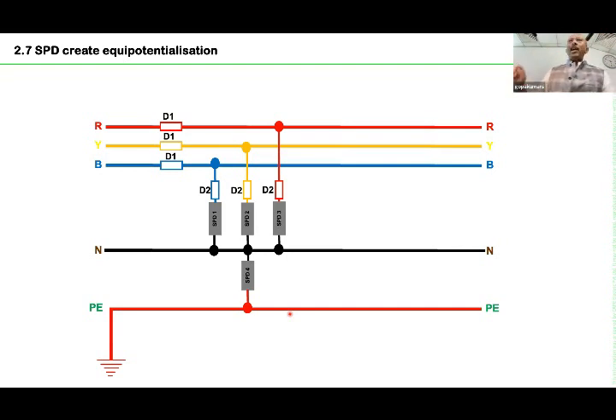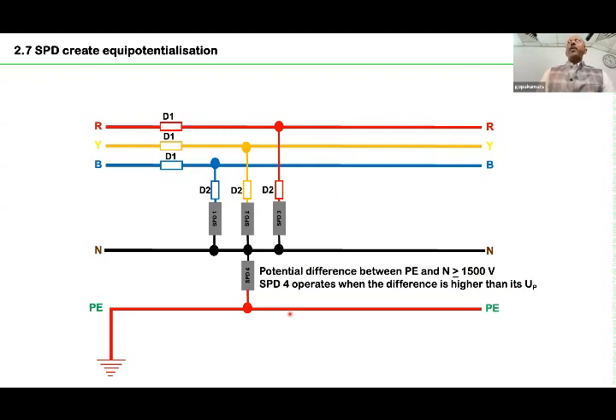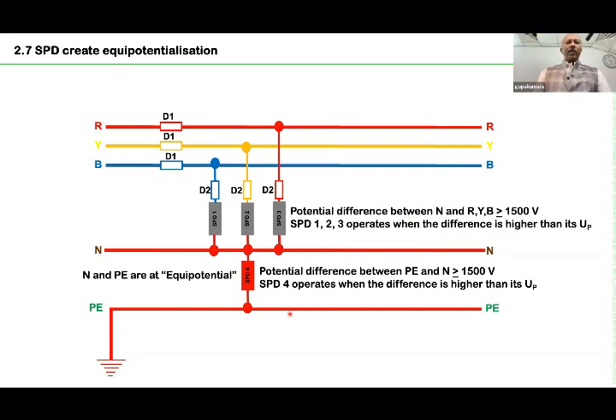Then what happens? Now the potential of the earth wire is very high. SPD number 4 operates and it connects the earth and the neutral. Suddenly your neutral and earth are connected together very fast. Maybe in a few nanoseconds this happens, or maybe in 2500 nanoseconds. So practically, between neutral and earth, you have connected it. The earth potential is now available in the neutral. Between earth and neutral there is no potential difference, but the neutral potential is very high with respect to a faraway place. Then the other three SPDs also operate, and suddenly all the lines plus neutral plus earth, everything is connected together. As a result, there is no potential difference. And if you look at an equipment which is connected downstream of the SPD, there are certain conditions that apply.